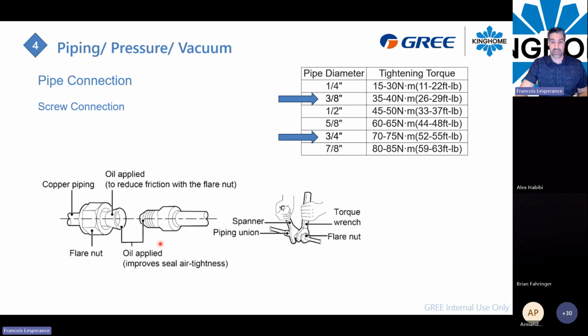And by doing this, and also by adding some oil, you will reduce the friction. You will help the flare nut move around the threads and not grip the copper and make it twist at the same time. By just moving the flare nut on the threads, you will make sure you have enough pressure and maintain that good connection over the years.